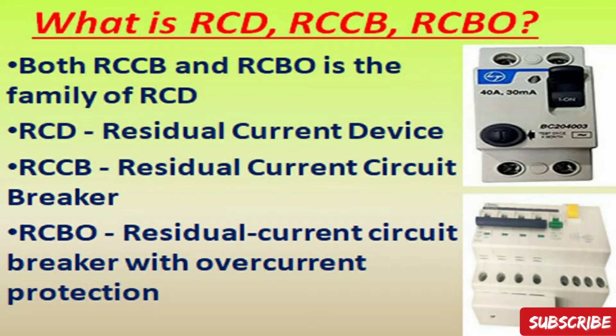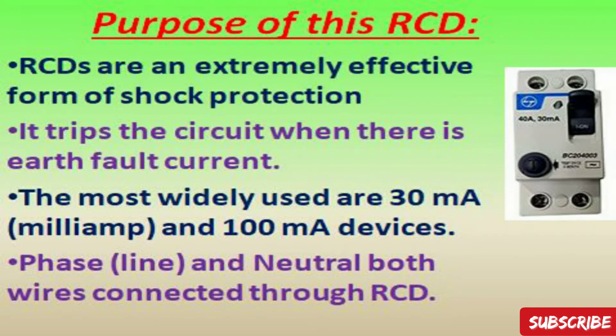RCDs are an extremely effective form of shock protection. They trip the circuit when there is an earth fault current in the load system. The most widely used RCCB ratings are 30 milliamps, which is used for human protection, and 100 milliamps, which is used for equipment protection.